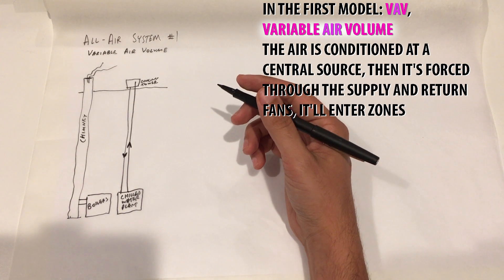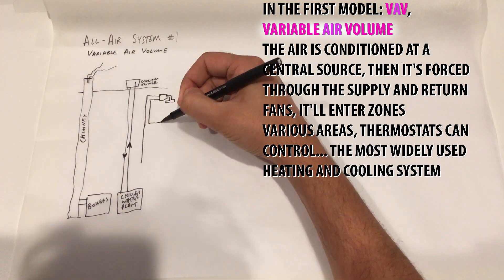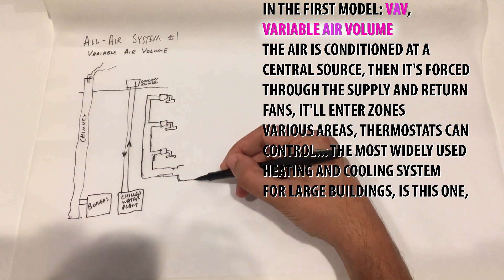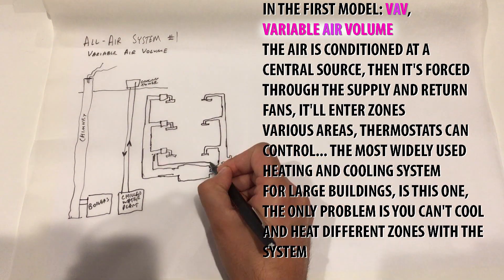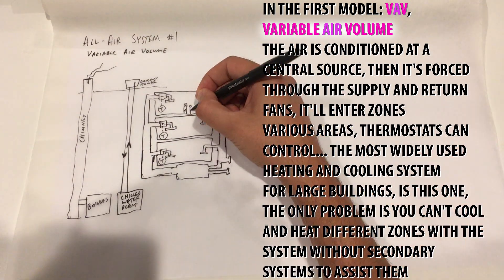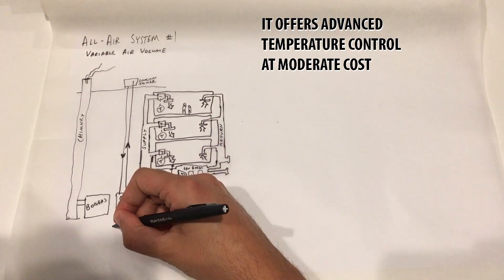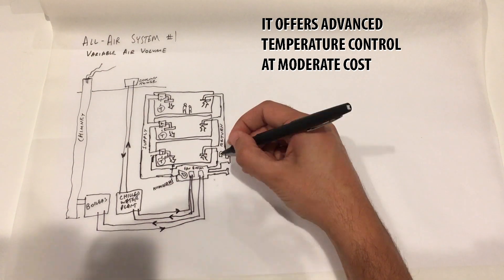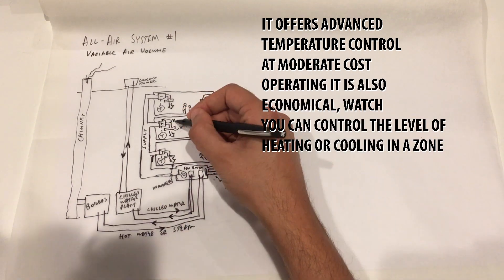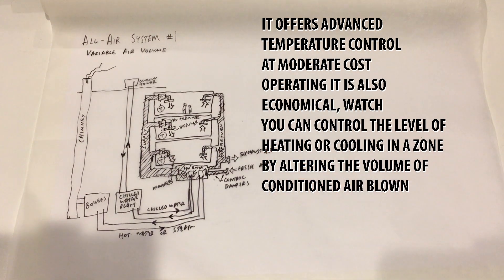With VAV, air enters various zones and thermostats control the temperature. It is the most widely used heating and cooling system for large buildings. The only problem is you can't cool and heat different zones simultaneously without secondary systems. It offers advanced temperature control at moderate and economical operating cost. You control the level of heating or cooling in a zone by altering the volume of conditioned air blown.